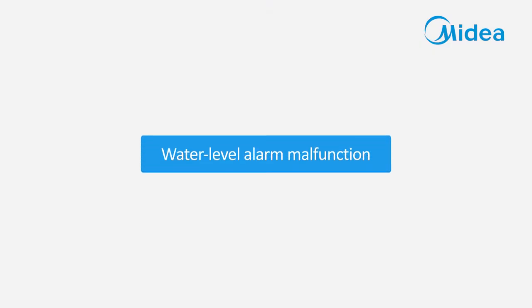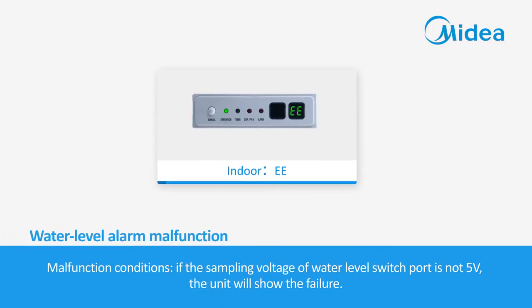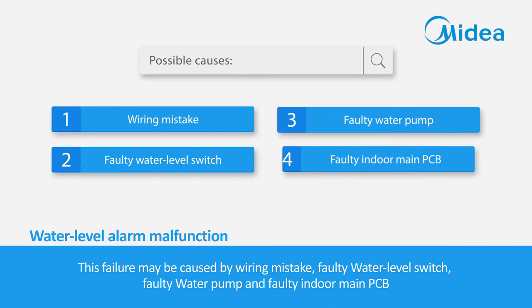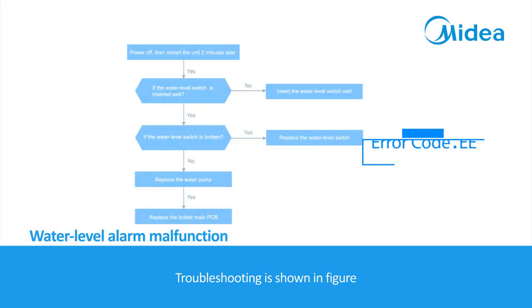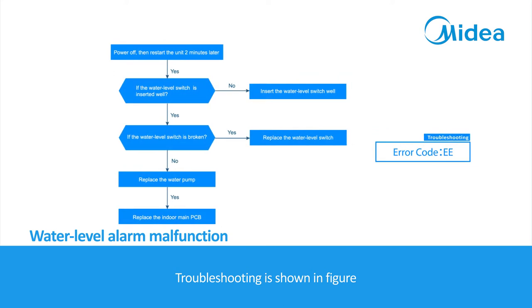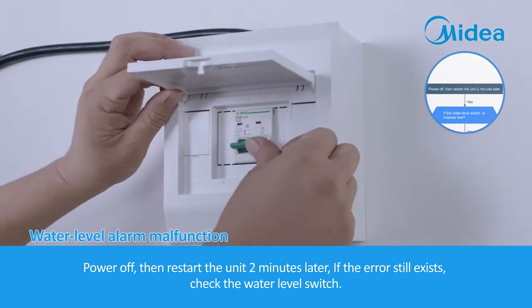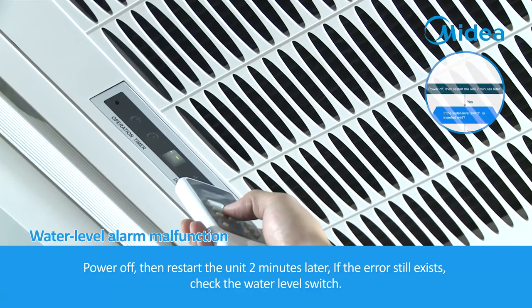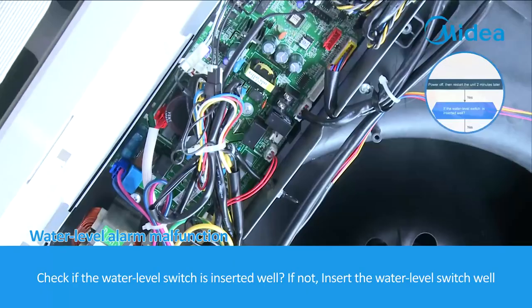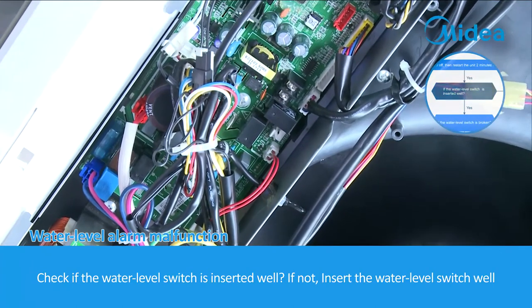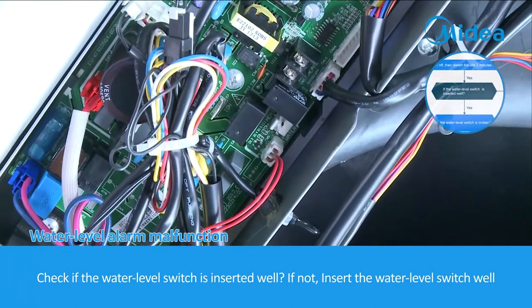Water level alarm malfunction. Malfunction conditions: if the sampling voltage of the water level switch port is not 5 volts, the unit will show the failure. This failure may be caused by wiring mistake, faulty water level switch, faulty water pump, or faulty indoor main PCB. Troubleshooting: power off, then restart the unit 2 minutes later. If the error still exists, check the water level switch. Check if the water level switch is inserted well; if not, insert it properly.